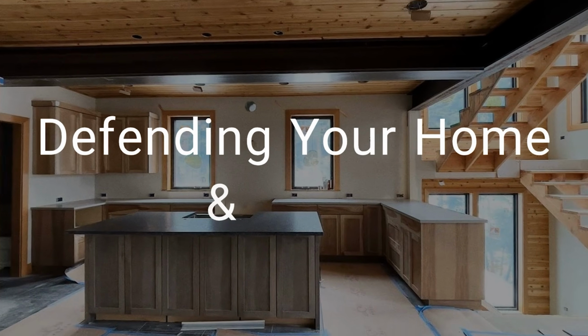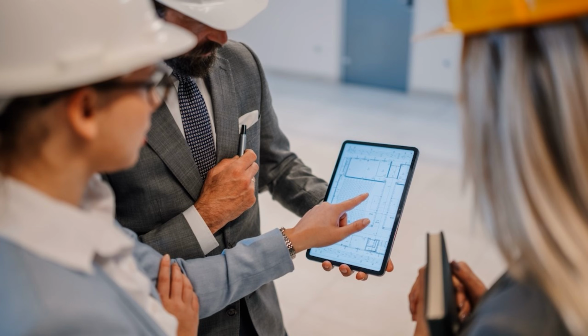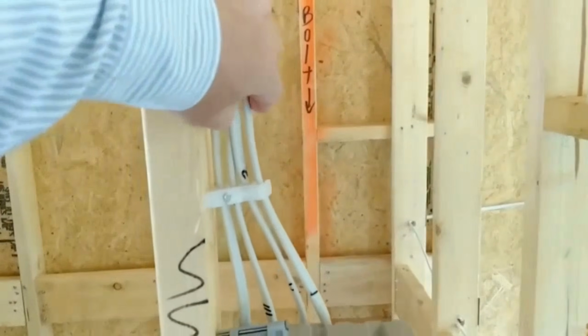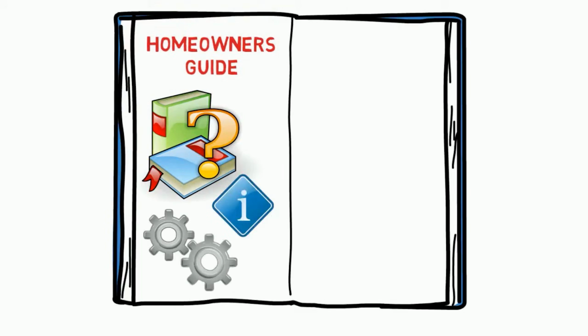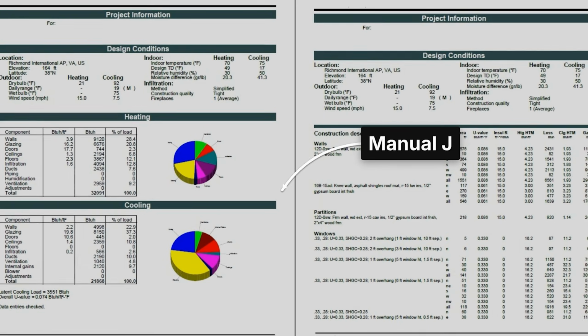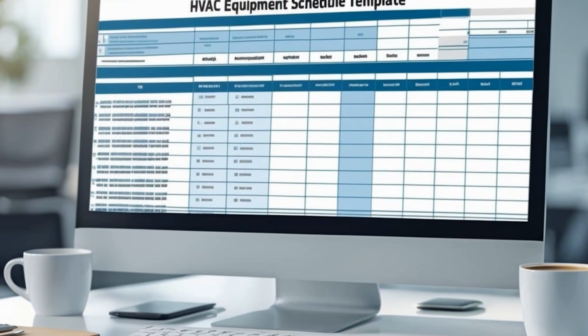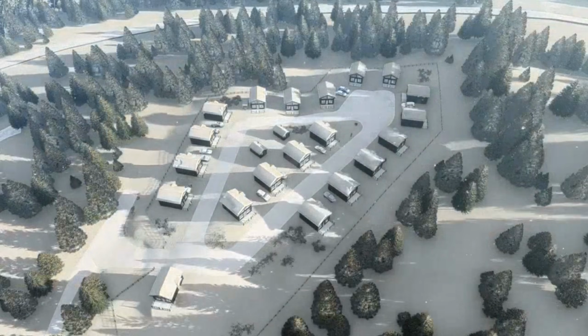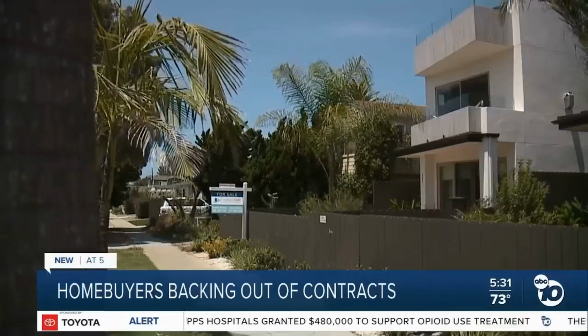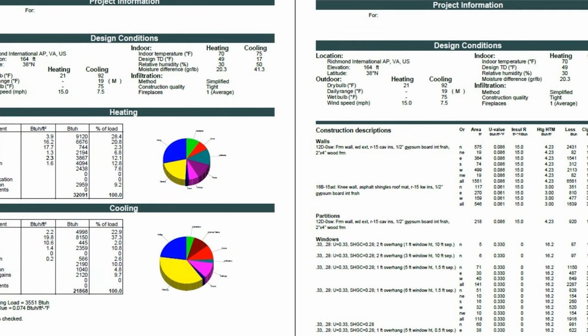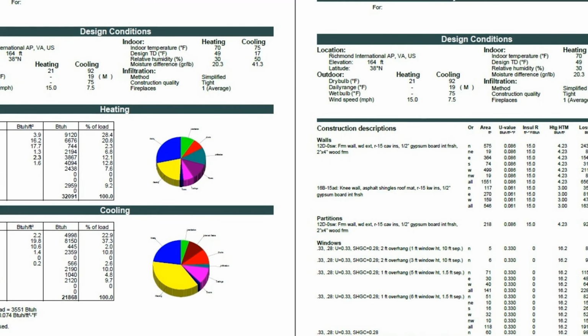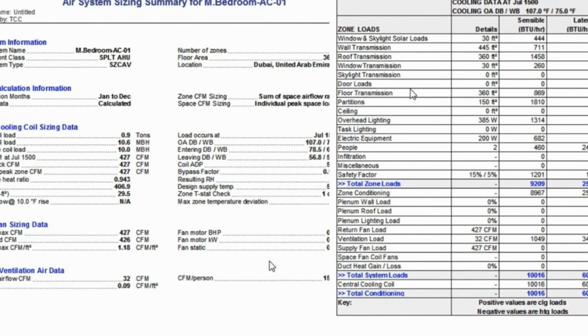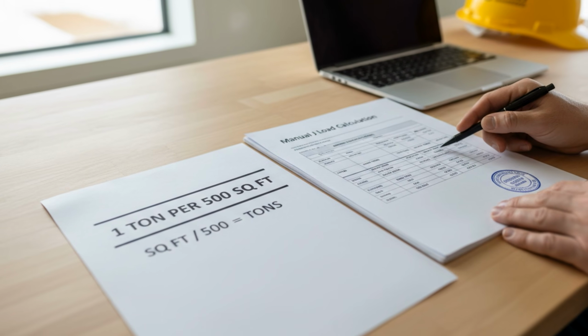So what do you do? You stop accepting the rule of thumb. You start demanding the calculation. If you are buying new construction, you have one moment of leverage before the drywall covers everything. Use it. Before you close, demand a copy of the Manual J load calculation for your specific home, not a template, not a generic subdivision document: your home's orientation, your lot's exposure, your window specifications. If the builder cannot produce it, that is your answer. A legitimate Manual J report is a multi-page engineering document with room-by-room heat gain and loss tables. A one-page spreadsheet with a square footage formula is not a Manual J calculation.